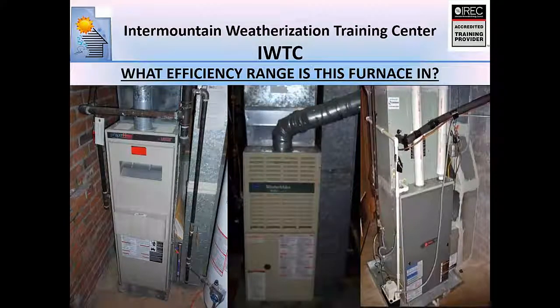There we go. So first thing we want to start with is quickly, visually, how can I tell what these furnaces are? I've got 3 furnaces up here, this one, and this one. All 3 of them fall into a different efficiency category. It's super easy to tell just by looking at the front of the furnace. So we'll start with this. Everyone notice this one's got a great big hole in the front door. It's called a draft diverter or a draft hood. Any furnace that has this on it falls into the 60% or what we classify as 60% efficient range. We'll talk about this draft diverter or draft hood here shortly.